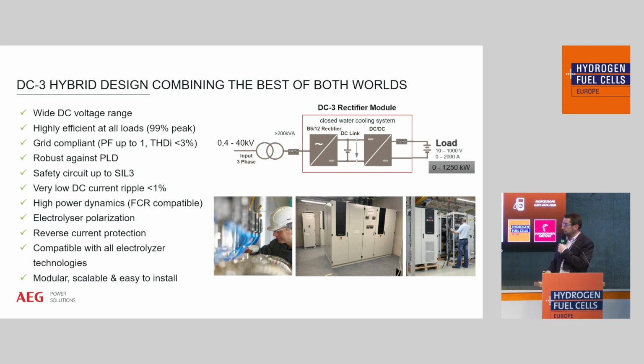I'd also like to highlight that the thyristor-based AC-DC converter is robust and protects the rest of the equipment against power line faults. We also have an integrated safety circuit up to SIL3, current ripple below 1%, and high power dynamics compatible with the frequency containment reserve market. We have integrated electrolyzer polarization and reverse current protection, and we're compatible with all electrolyzer technologies.